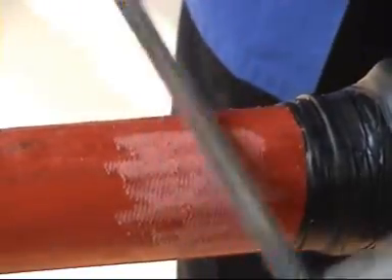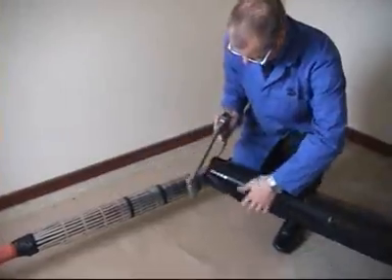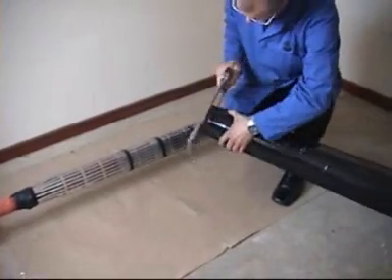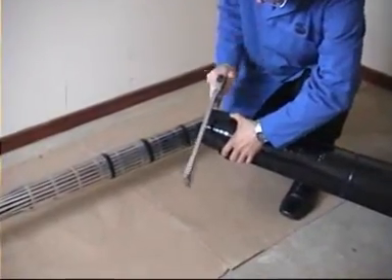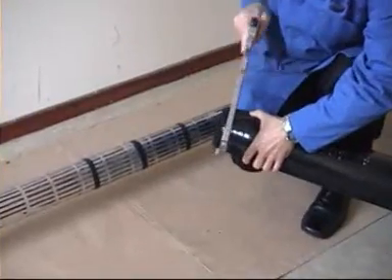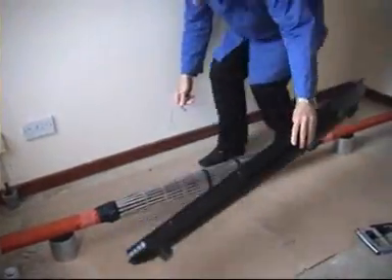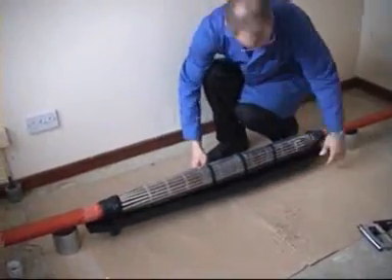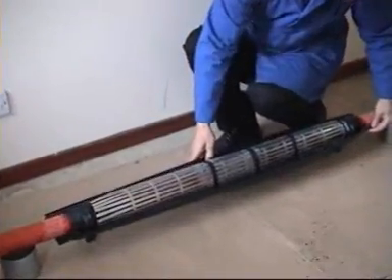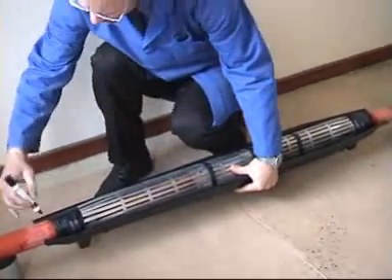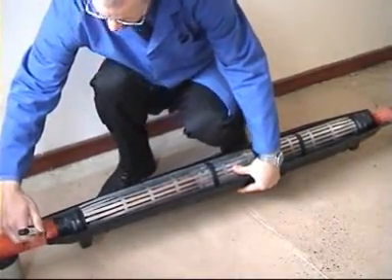Rough up the outer cable sheaths on both cable sides to provide a good adhesive key. With a hacksaw cut down the tapered part of the shell in order to fit the cable diameter. Now offer the shell up to the cable and make a mark on the outer cable sheath at both ends.